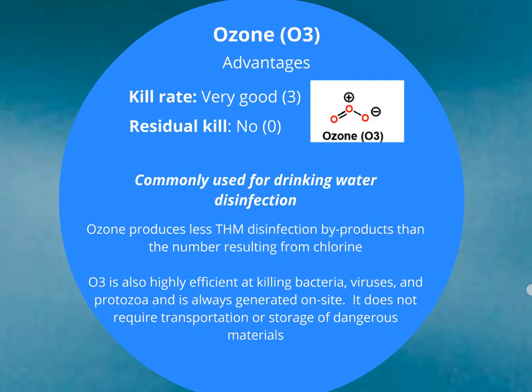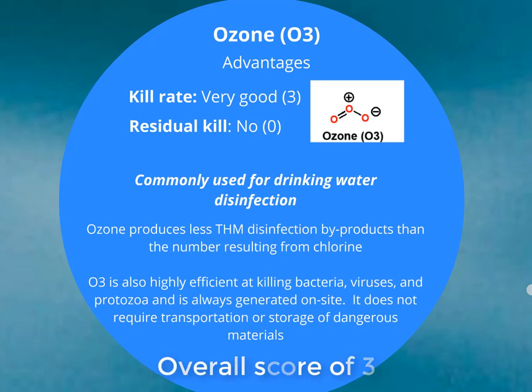Ozone, also known as O3, has a very good kill rate and is commonly used in drinking water disinfection. It produces less THM (trihalomethane) disinfection byproducts than those resulting from chlorine. It's also very highly efficient at killing bacteria, viruses and protozoa, and it's always generated on site — it doesn't require transportation or storage of dangerous materials.